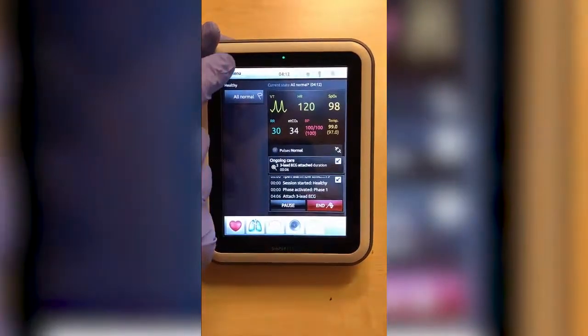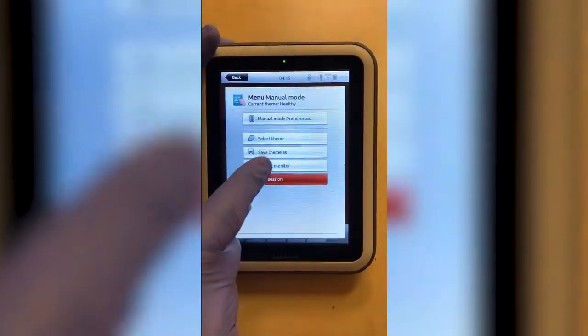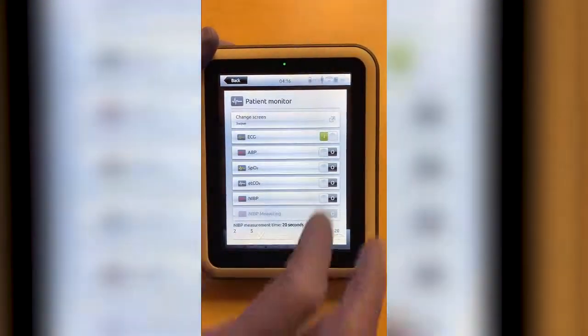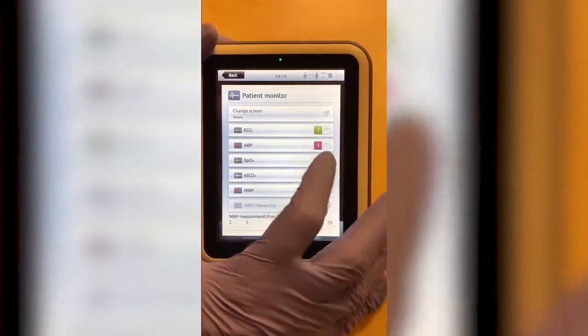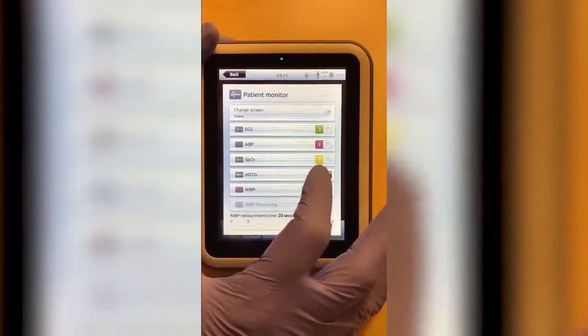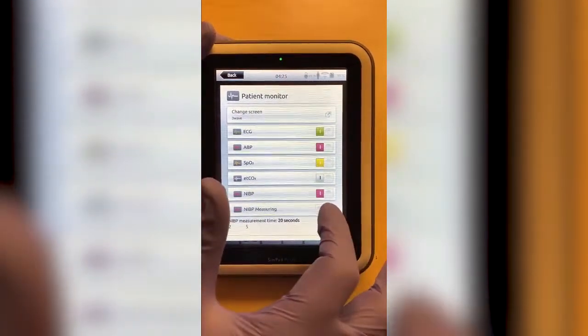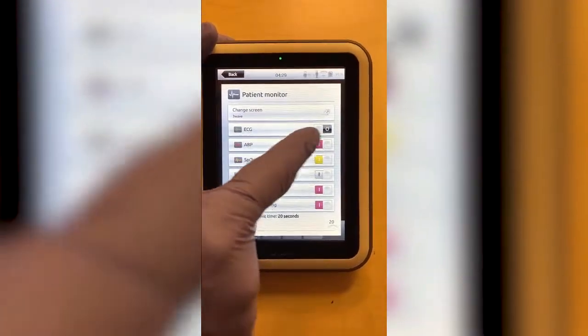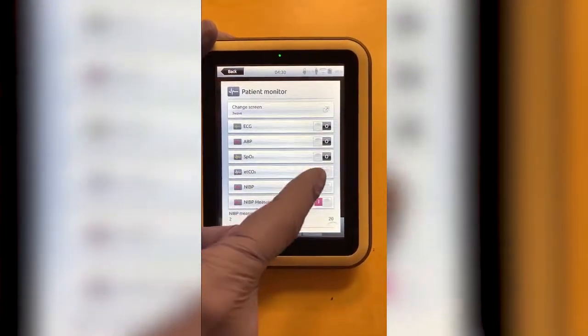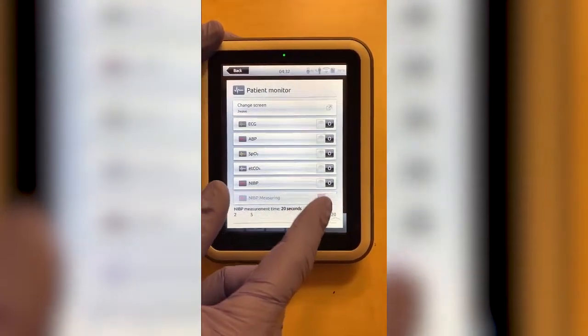From the main menu, go to menu, then hit patient monitor and you can turn the feature on or off. Green means active and grayed out means inactive. This is activating on the vital signs monitor — now I'm deactivating all those features so they're not streaming any vitals.